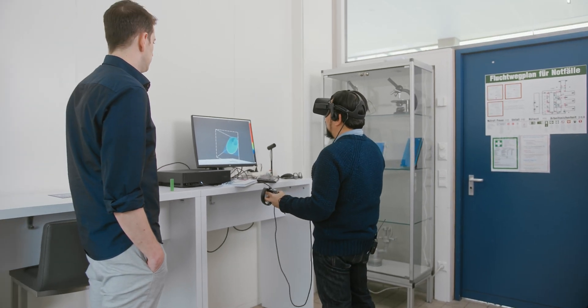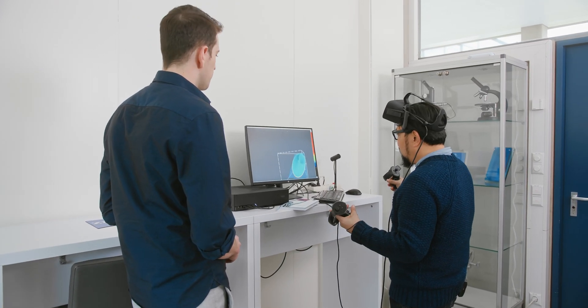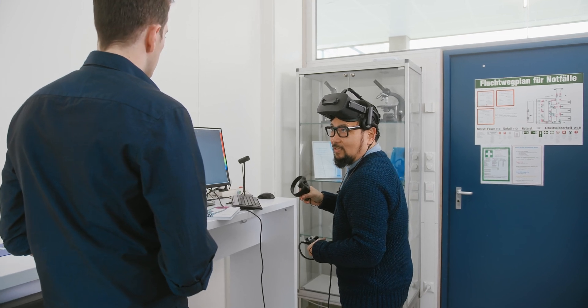Okay Andres, other than being super cool, what's going on in here? So here we have a CT data set and we can look inside the battery without destroying it. We can check if the battery is assembled the right way, are there any safety margins too small, is there any welding voids inside, or is the whole geometry in the right place. We're able to see inside because of the CT scan — we can definitely see structures and what's going on in there.